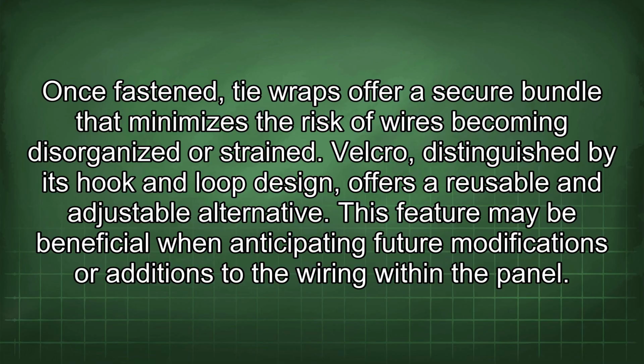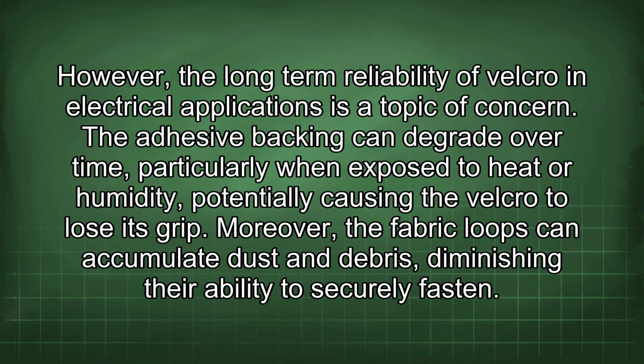This feature may be beneficial when anticipating future modifications or additions to the wiring within the panel. However, the long-term reliability of Velcro in electrical applications is a topic of concern. The adhesive backing can degrade over time, particularly when exposed to heat or humidity, potentially causing the Velcro to lose its grip. Moreover, the fabric loops can accumulate dust and debris, diminishing their ability to securely fasten.